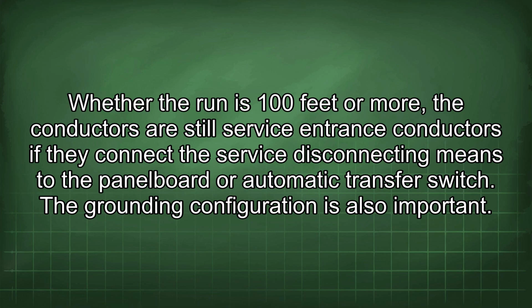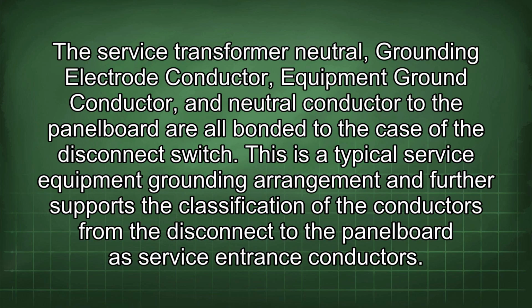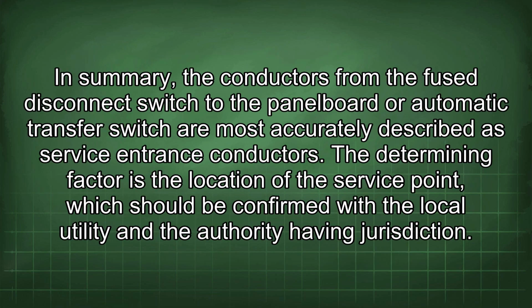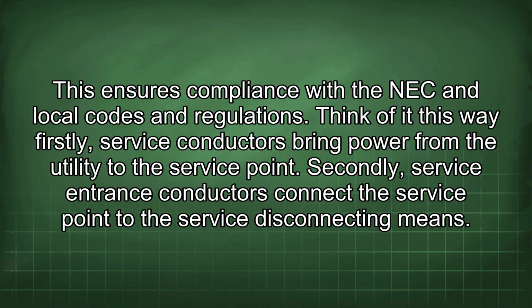The grounding configuration is also important. The service transformer neutral, grounding electrode conductor, equipment ground conductor, and neutral conductor to the panel board are all bonded to the case of the disconnect switch. This is a typical service equipment grounding arrangement and further supports the classification of the conductors from the disconnect to the panel board as service entrance conductors. In summary, the conductors from the fuse disconnect switch to the panel board or automatic transfer switch are most accurately described as service entrance conductors. The determining factor is the location of the service point, which should be confirmed with the local utility and the authority having jurisdiction. This ensures compliance with the NEC and local codes and regulations.